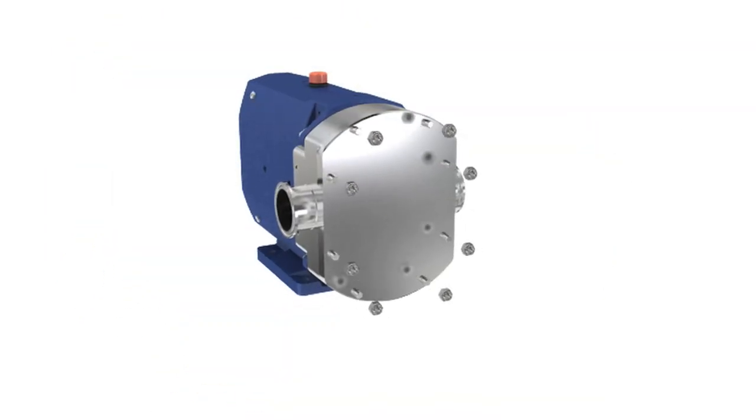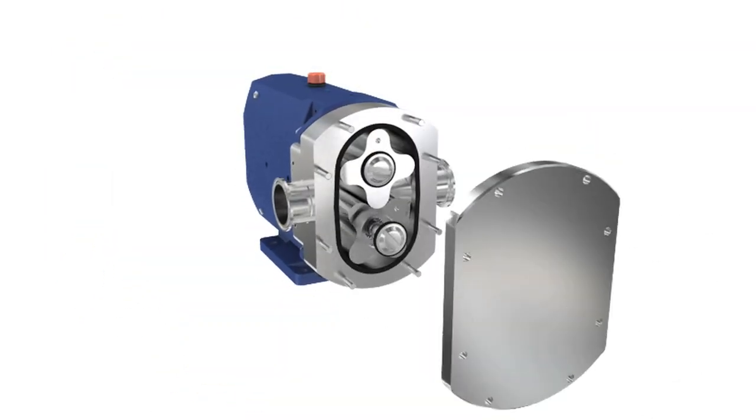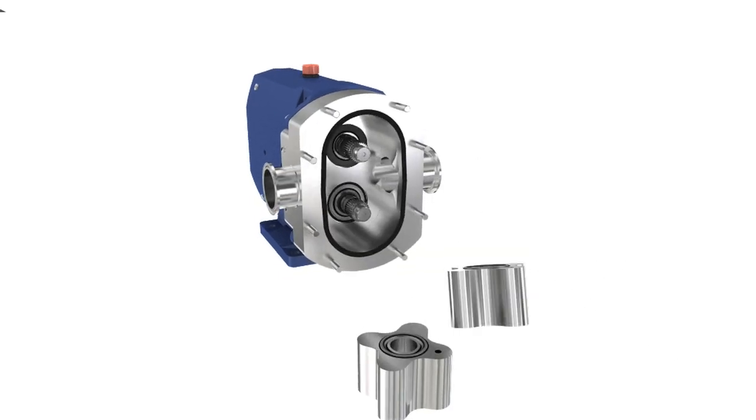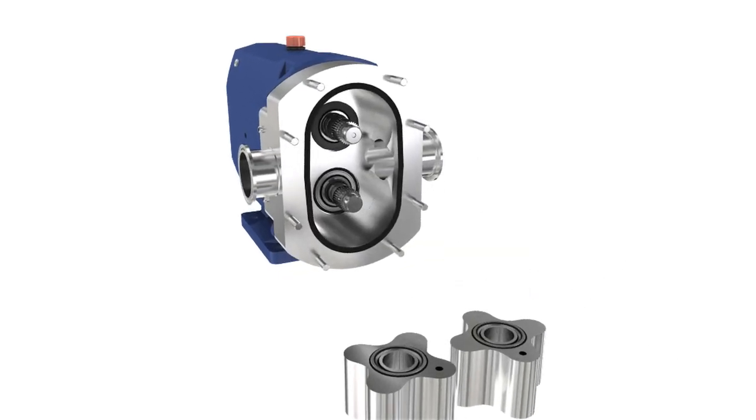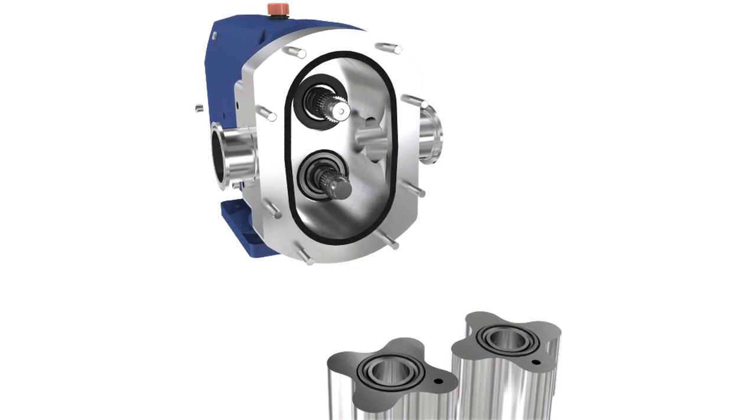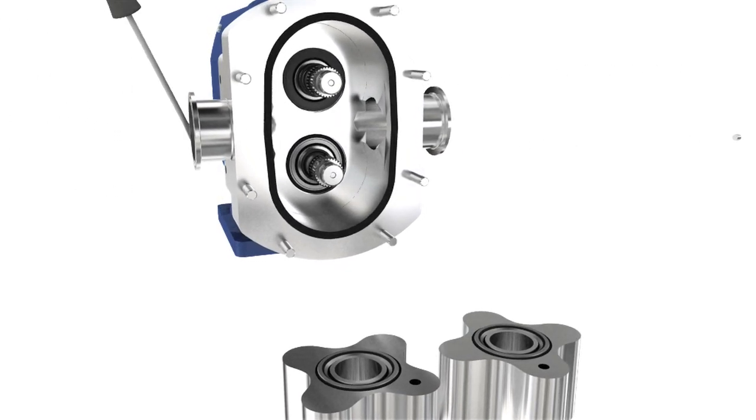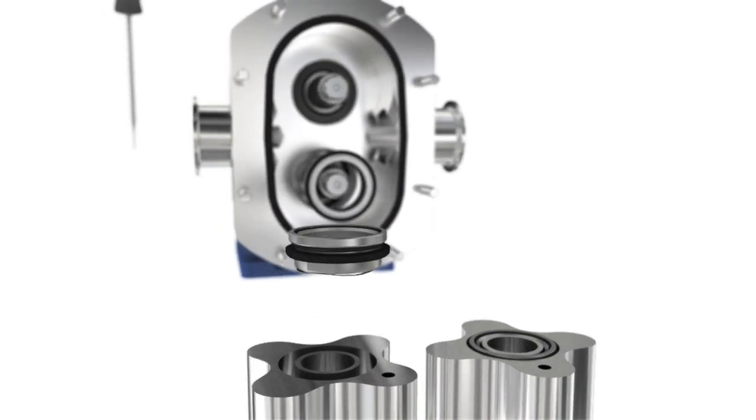One of the most critical components in any pump is the seal. The SX features front-loading seals. This allows inspection or repair without the need to remove the rotor case from the pump or the pump from the process line. This highly simplifies maintenance and greatly reduces downtime.